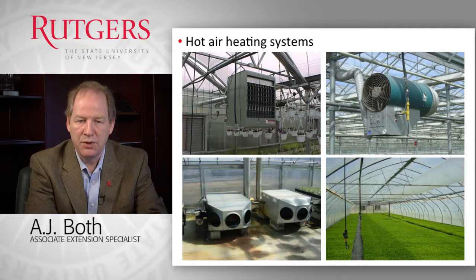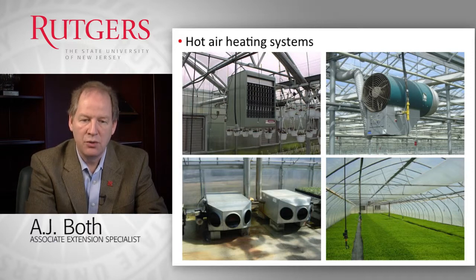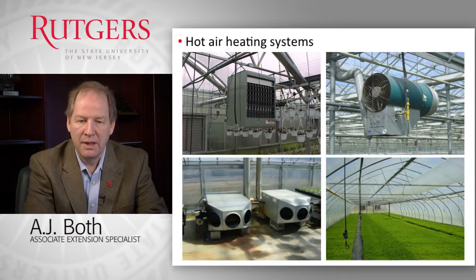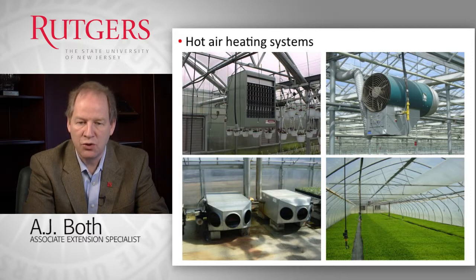More common are hot air heating systems. We have unit heaters typically installed along side walls that blow jets of warm air into the greenhouse. An issue of how we provide combustion air and expel that combustion air is a concern. Sometimes we see systems that have separated pathways for incoming combustion air as well as exhaust air, to prevent any potential contamination of the greenhouse environment by gases that may be harmful to plants.